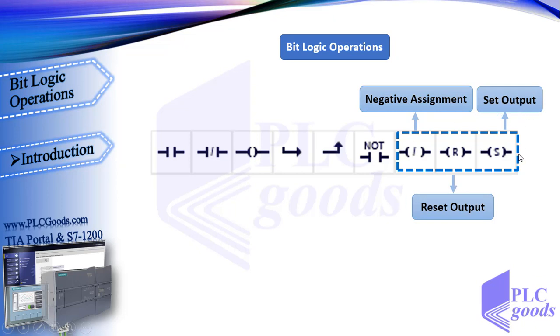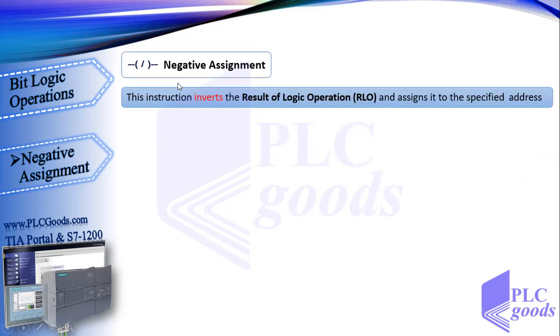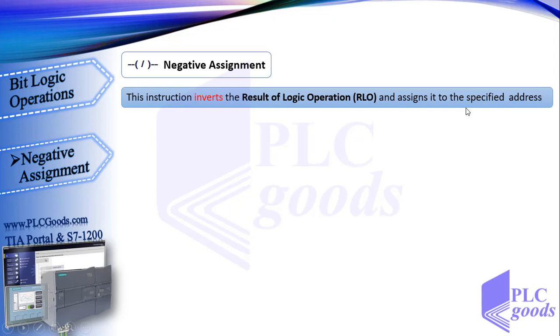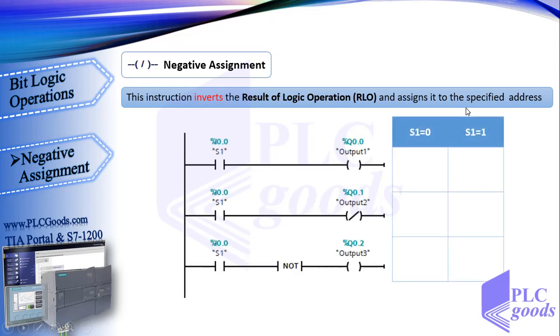First let's see negative assignment. This is the ladder symbol of negative assignment instruction. This instruction inverts the result of logic operation, RLO, and assigns it to the specified address. If you remember in ladder language, RLO is the same as virtual power.